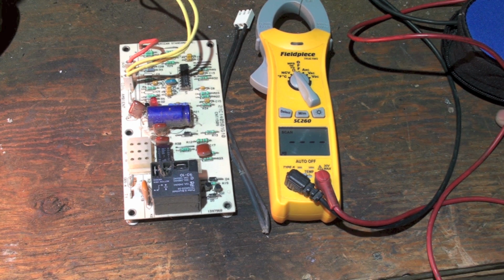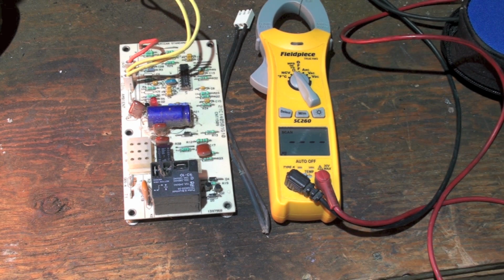In a pinch, I would take both of the probes and I would compare them if they're at the same temperature and see if they're the same. If they're reasonably close to each other, they're probably okay. But then you'll take one of them, you'll warm it up and see if it changes. Take the other one, warm it up, see if it changes. That's a quickie if you don't have any factory specs to go by. These boards do fail. The sensors fail more commonly.